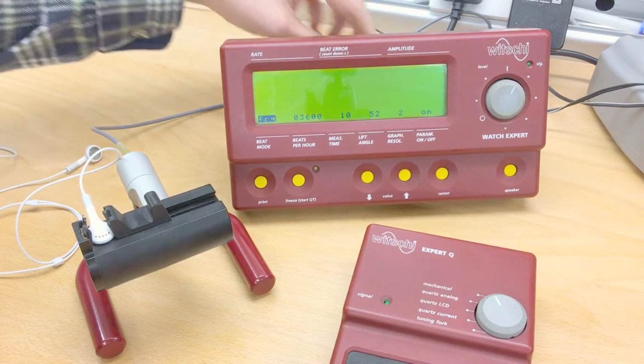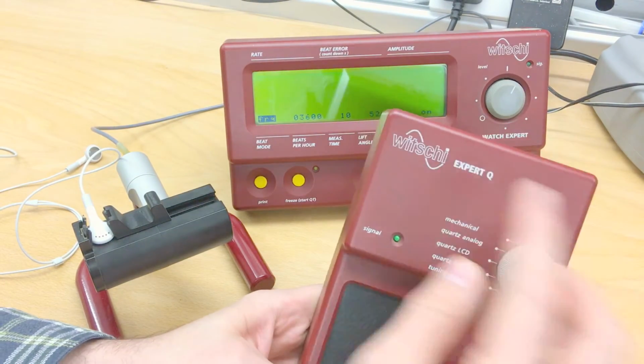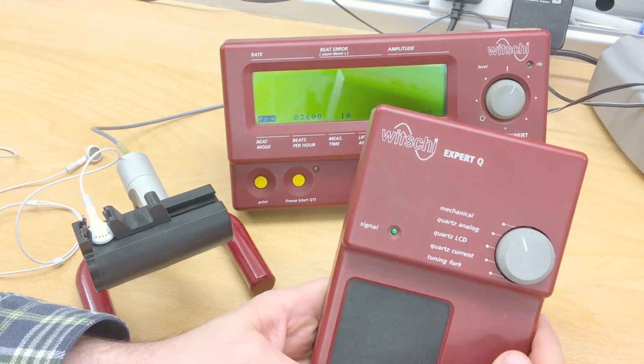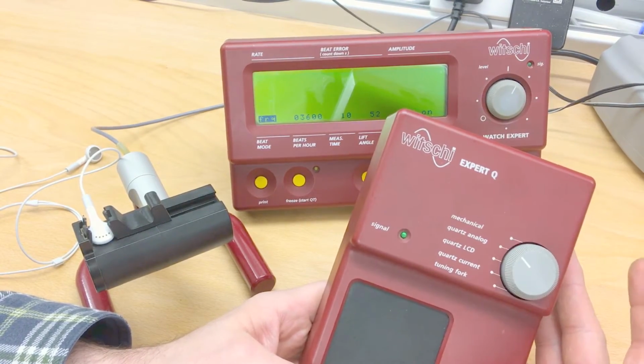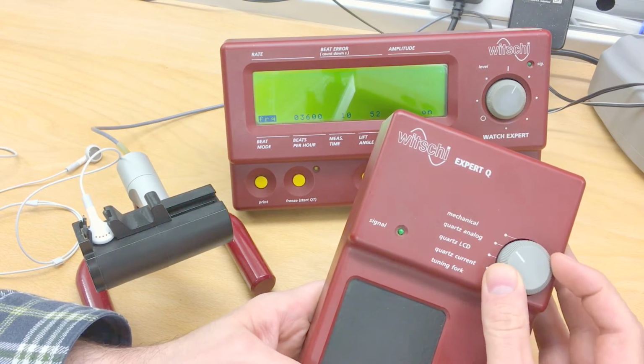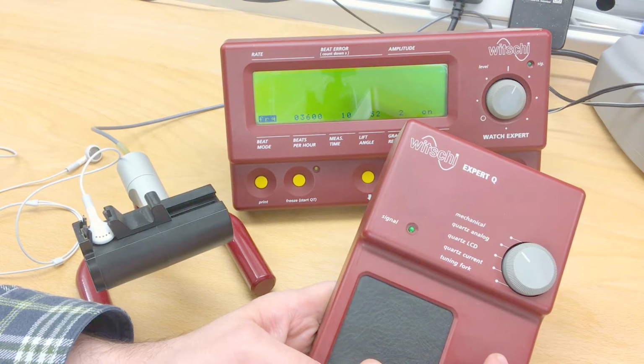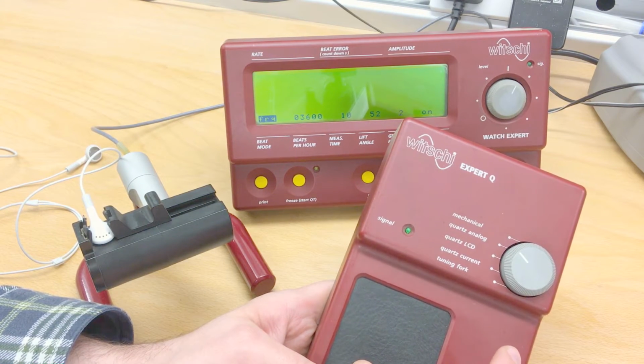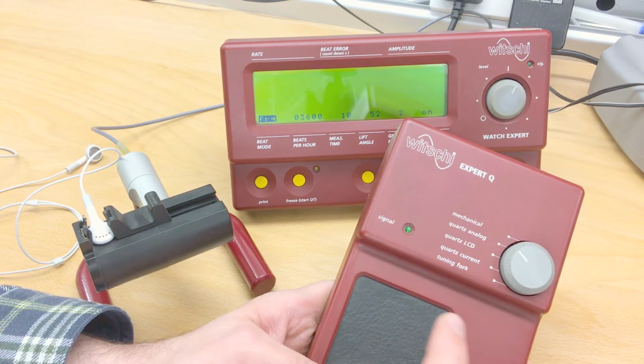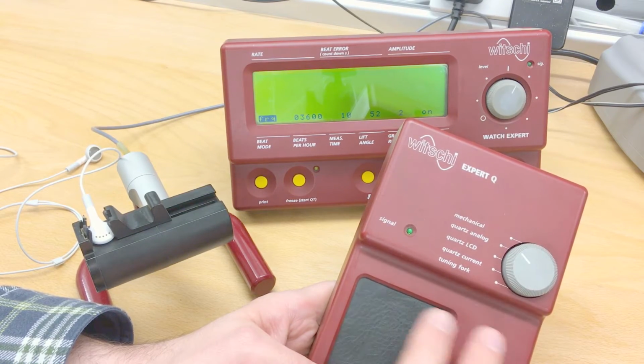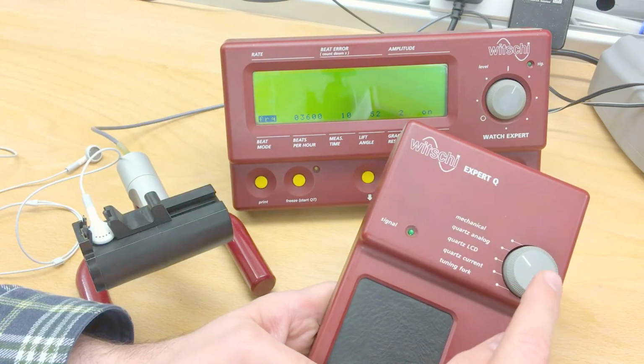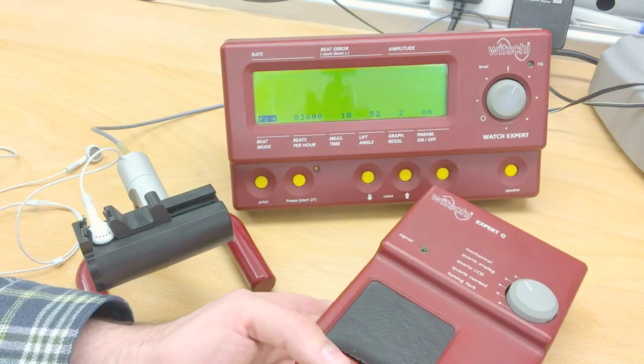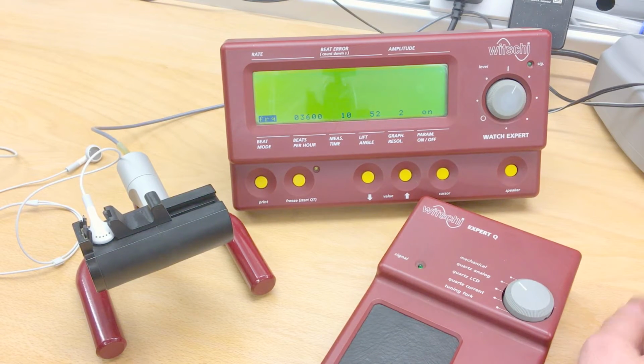So we could pass the mechanical signal through this into there, and if we had that set to mechanical, it would simply loop the signal straight into the machine. It's when we click this over to the quartz settings that more magic happens. Now, this device, as I said, was sold as an extra, is full of circuitry and predominantly op amps and differential amplifiers, which I'm guessing gives a very crisp pulse, which is then fed into here. But I also believe that it must send some message to the mothership that it's to expect this crisp pulse, and I haven't been able to decipher what that code is in order to override this machine's expectations.